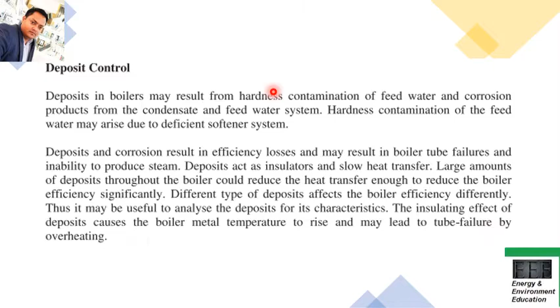So all these are aspects you should understand, and also the insulating effect of the deposit causes the boiler metal temperature to rise and may lead to tube failure by overheating. You have to understand that you have to control the deposit as much as possible, so that you have a better system, better boiler efficiency, better performance of the boiler, and less corrosion effect, and also there will be no insulating effect of the deposits, which would cause the boiler metal temperature to rise and may lead to tube failure by overheating. So all these things will be controlled once you control the deposit formation, friends.